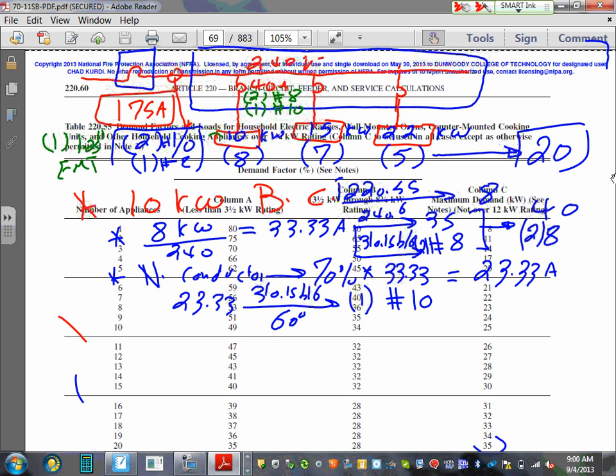So the second one, the second range, what was the size of the second range? 15 kW. Okay. Now, for a 15 kW branch circuit, the code allows you to use the same table for branch circuit ranges. Okay, so the same table, what's the demand for 1 kW under C? 8 kW. Did you guys hear me? 8 kW. Hold your horses. Now, we're sizing the branch circuit for that 15 kW. There's how many of them? There's 7 of them. But we don't care how many of them because we're not sizing a feeder. We're sizing just home runs for each one of them.